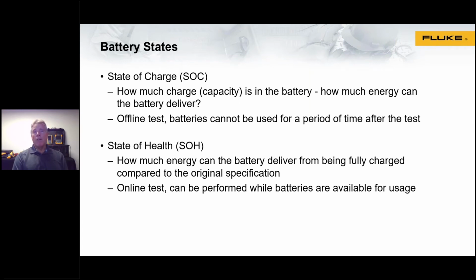So oftentimes for health measurements, kind of much in the analogy of using a thermal imager for screening, state of health measurements, on the other hand, is a test that can be used when the batteries are available for service or are in service. So it's essentially using a health measurement, which we'll explore. It's mainly internal battery resistance to indicate how much energy the battery can deliver from being fully charged compared to the original spec.